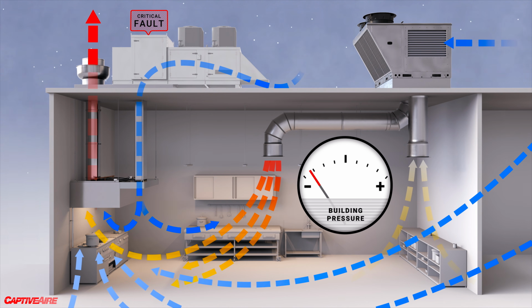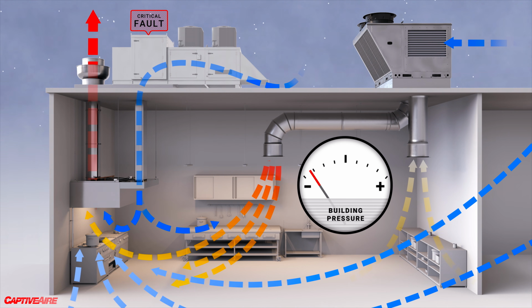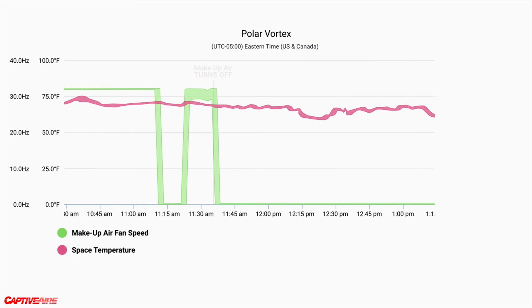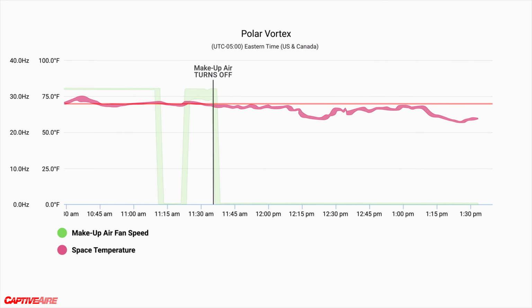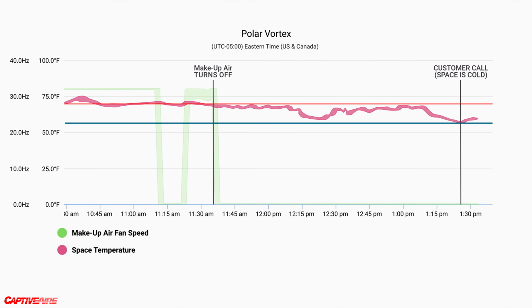So the day that this went down, we got a call that the building's getting cold quickly. We pulled it up on CASLink. We saw the temperatures go from their 70-degree set point down to 58 degrees before we got that call for a service saying, hey, our space is extremely cold. Because of the polar vortex calling in all these different techs, we couldn't get a tech out there until Friday. And they're expecting to hit the lows of this polar vortex on Thursday, so in that window. So we know we're facing a situation where they're going to potentially have to shut that store down completely if we can't get a resolution.